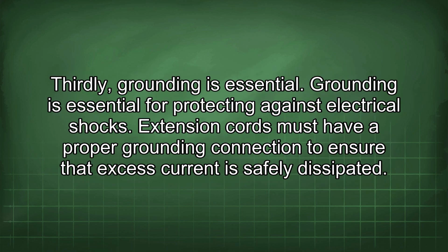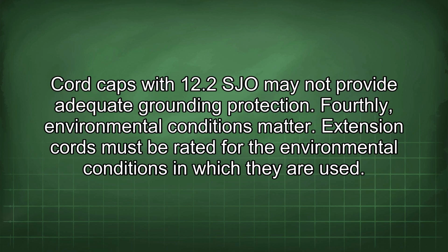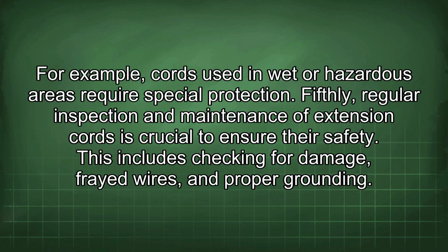Thirdly, grounding is essential. Grounding is essential for protecting against electrical shocks. Extension cords must have a proper grounding connection to ensure that excess current is safely dissipated. Cord caps with 12.2 SJO may not provide adequate grounding protection. Fourthly, environmental conditions matter. Extension cords must be rated for the environmental conditions in which they are used. For example, cords used in wet or hazardous areas require special protection.